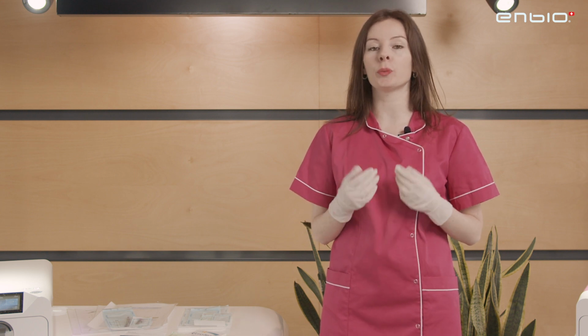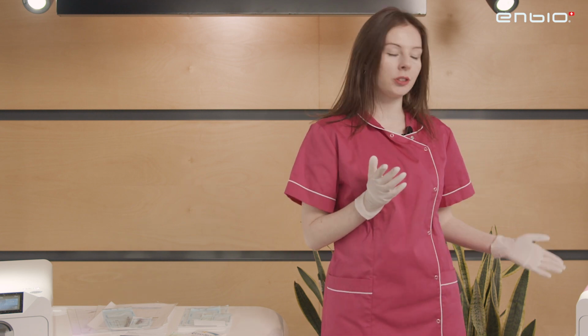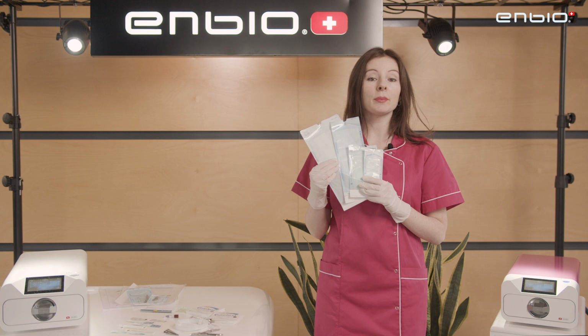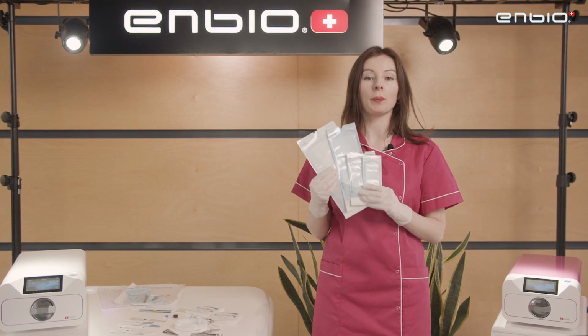Let's see how we can prepare the tools for sterilization. First of all, it is important to remember to always use protective gloves for the whole decontamination process. And to prepare the tools for sterilization, we recommend always to use sterilization pouches. But, for instance, if you are using the Enbio autoclave, you can sterilize as well the tools without any sterilization pouch. Here are some examples of sterilization pouches.